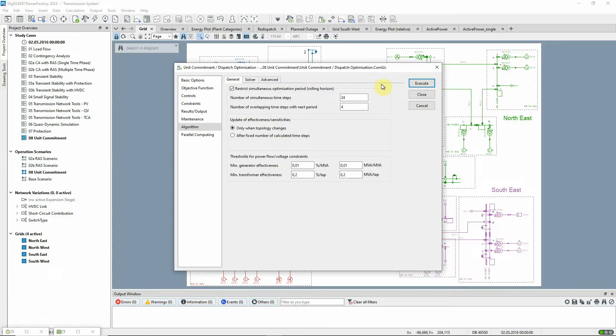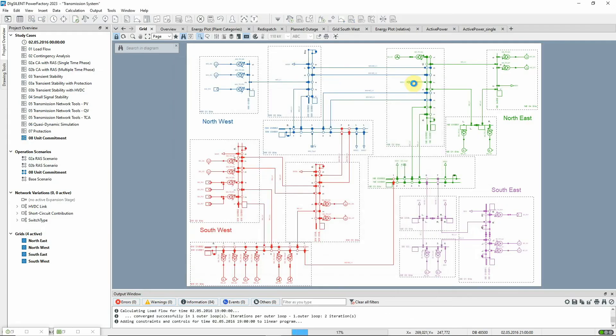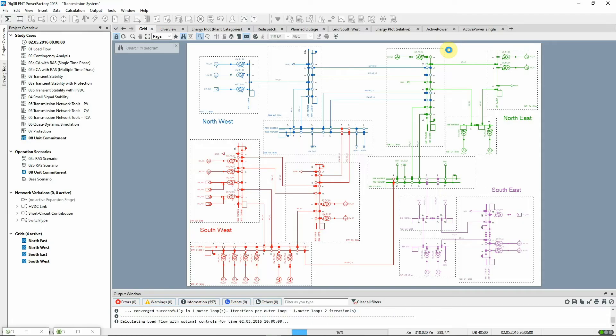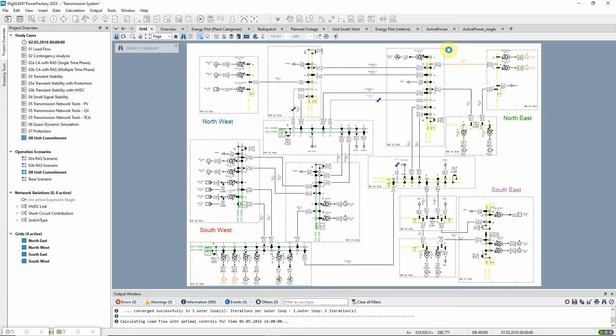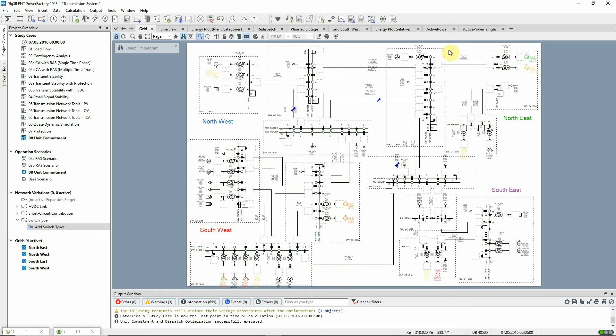We will now start the simulation. For a successful unit commitment and dispatch optimization run, it's necessary for the load flow to converge at every time step in the quasi-dynamic simulation because these results are used for the initialization and linearization of the mixed-integer linear problem that is solved in the unit commitment.